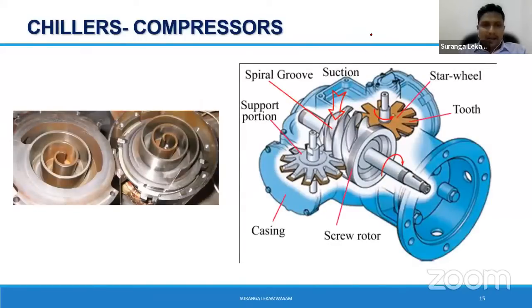So now regarding the chillers, I am happy to share some information about the compressor, because the compressor is the heart or the brain of the chill water system. Typically, the type of compressor varies depending on your chiller capacity. Let's say if you want a chiller of less than 100 ton, a very rare situation, but in that range, you will find chillers with scroll compressors, right?